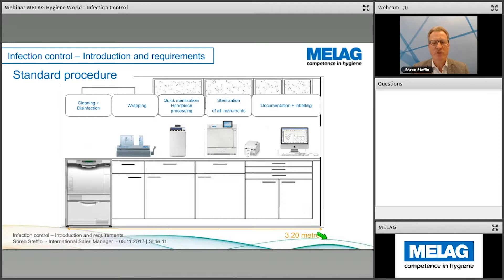In a lot of facilities there is no extra room and no big space for instrument reprocessing. The requirements keep increasing, with authorities demanding more and more, but the rooms do not grow. We have to adapt our higher expectations to existing facilities. With clever planning, good consultation by dealers, and experienced information, we can set up a proper line of instrument processing even in a smaller shelf line or smaller room. The biggest problem is having no knowledge about the ways and crossing all the different stations, bringing cross-contamination into the processing room. By good knowledge and good arrangement, we can avoid that.